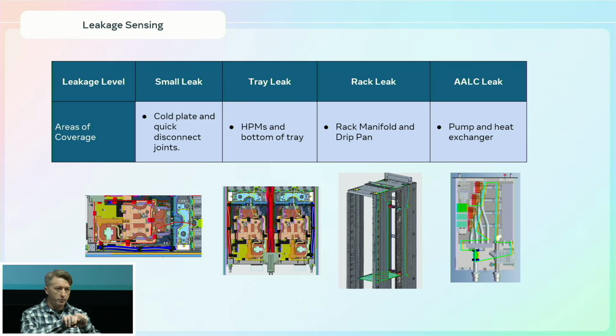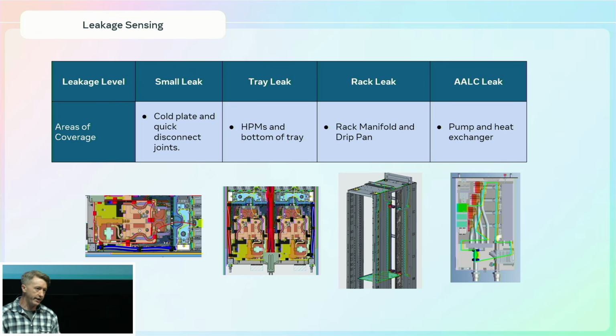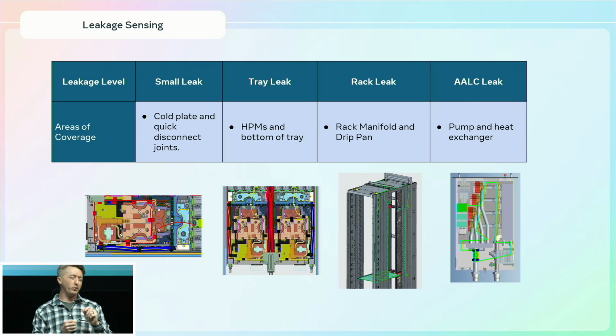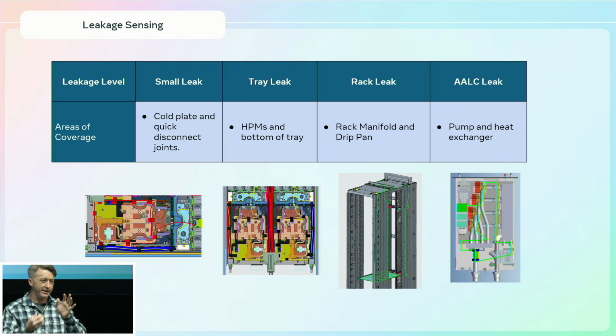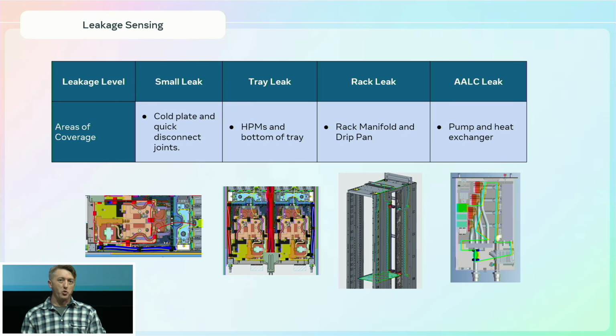Usually it's where the QDs would be, the first portion where something may start to dribble, there's some residual liquid. Usually, QDs, the cold plates, represent connection points where very likely a leak would probably start if you have some debris in the QD. Tray leaks are progressively more catastrophic, or more severe, perhaps.